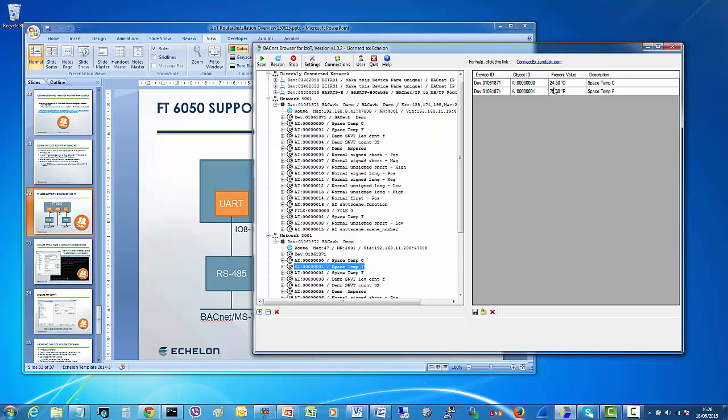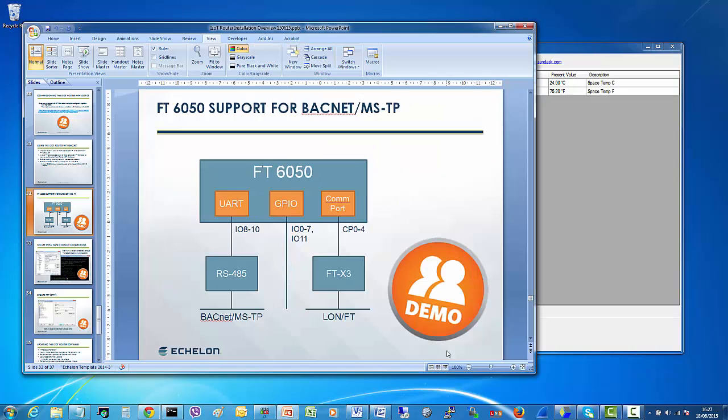And the key difference here to remember is that where LonWorks or IzoT will send data across the network typically in SI units, and it's up to the person at the end to interpret the data either in, say, SI or imperial format. BACnet servers have to send that data pre-formatted in the required format. So in this instance, our BACnet MSTP interface is sending directly in degrees F. So moving back to the presentation.